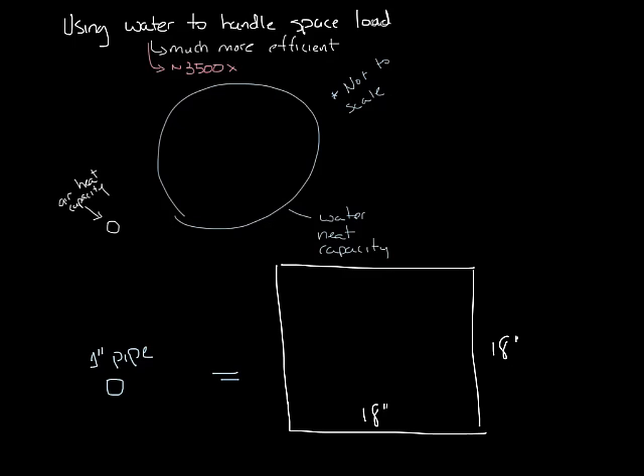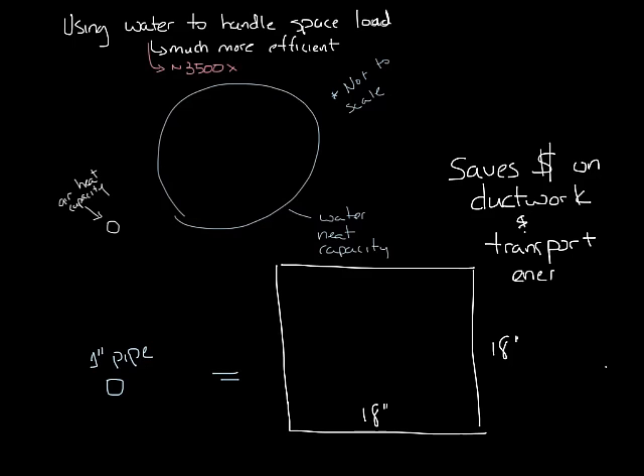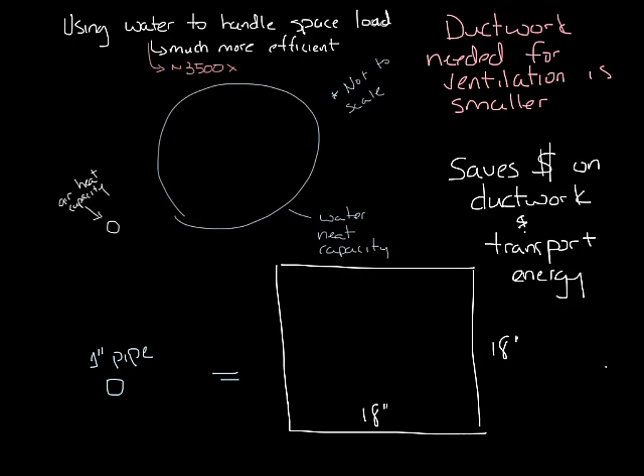This huge difference means that you can cool the space using piping that's 1 inch versus running larger ductwork throughout the building. This saves on the material cost of the ductwork in the building. It should also cost you less to transport that energy through the 1-inch pipe than the 18 by 18-inch ductwork. In a chilled beam system, you still have to run ductwork for the ventilation air though. But even though there is ductwork, it is much smaller because you only bring in enough air to handle the ventilation requirements, not handle the entire load of the space. The ductwork is more likely to be about 5 or 8 inches coming into the chilled beam supply air inlet.